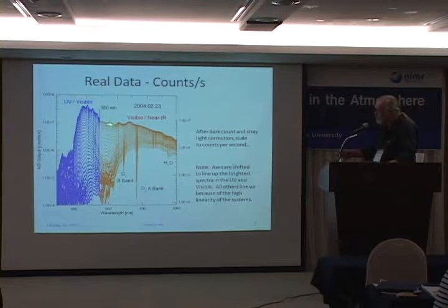And it shifted so that the top spectrum right here will line up. And you can see from the fact that all of these other spectra, going all the way down orders of magnitude, all line up still, that the whole system is extremely linear over a very large range of intensities. And that's another thing that you have to test your instrument for. If you just assume your instrument's linear, you may get some really bad surprises.